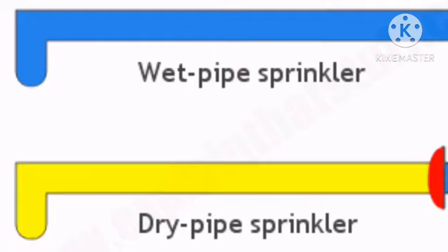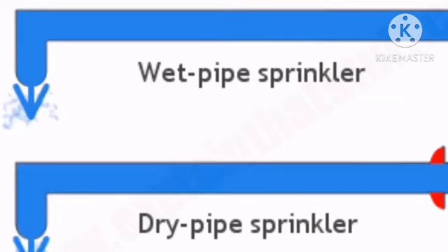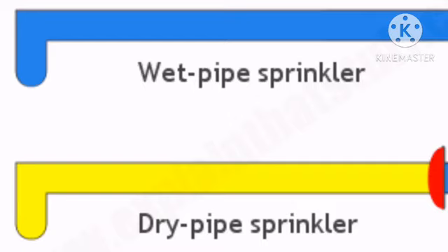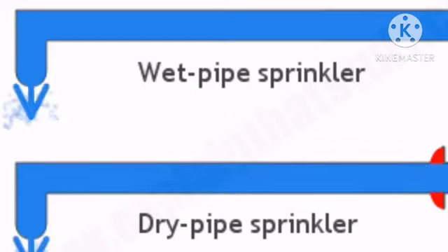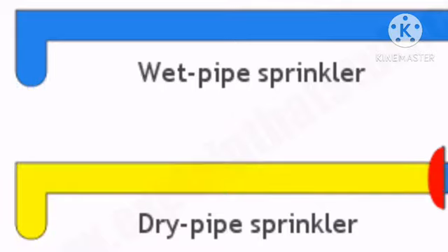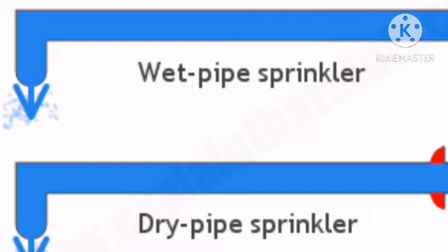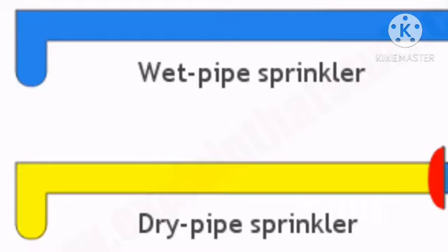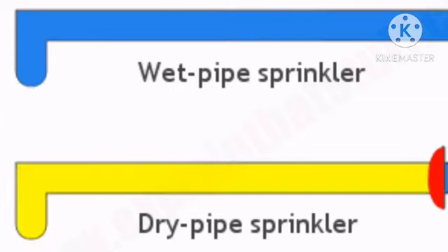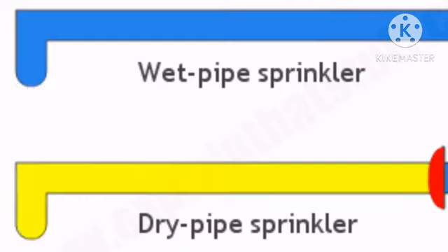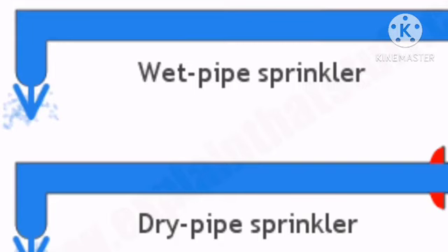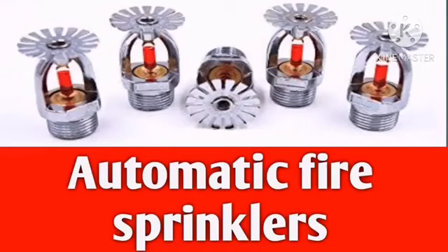Dry sprinkler systems use pressurized air in the pipe which exits before water escapes. Pre-action sprinkler systems are filled with air and water passes through if the smoke alarm or detector goes off. They are best used in locations looking to avoid accidental and unnecessary water damage such as libraries or data centers. Deluge sprinkler systems feature open nozzles and are common to industrial parks as they respond to hazards including flammable liquids spilling across a floor.